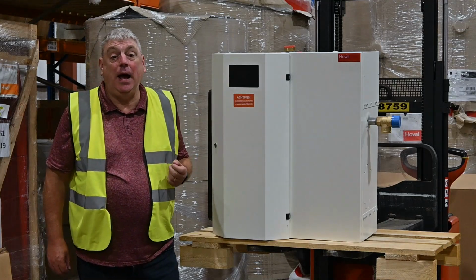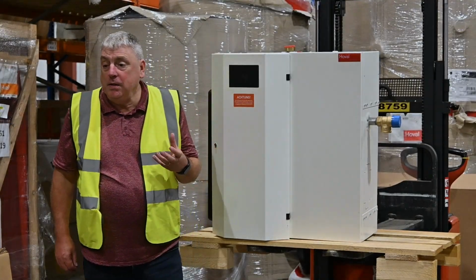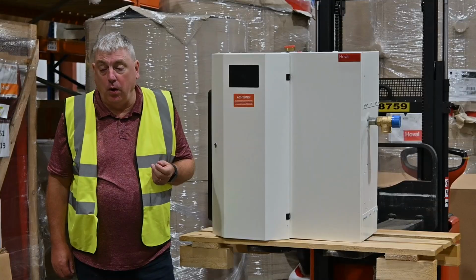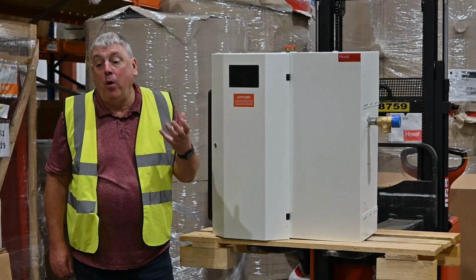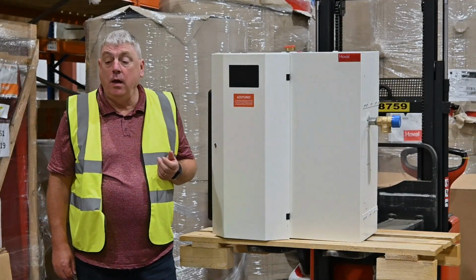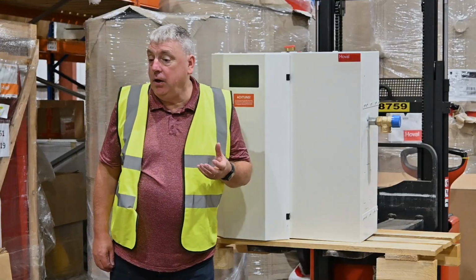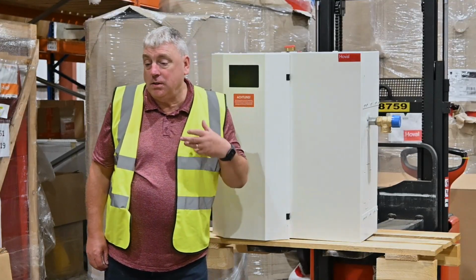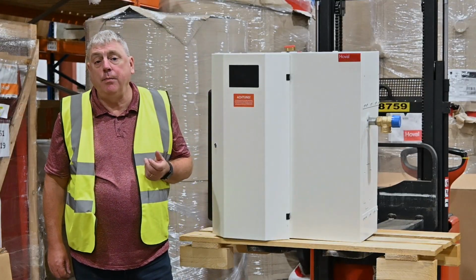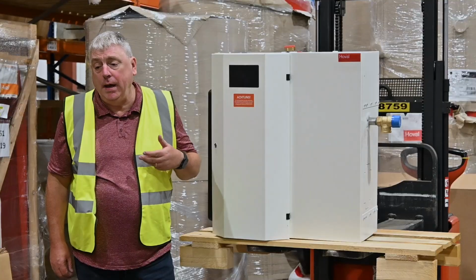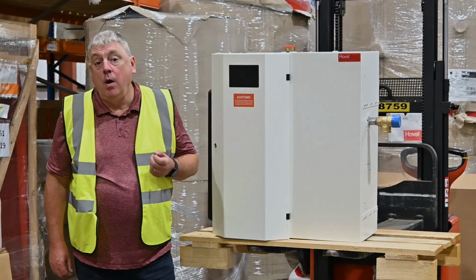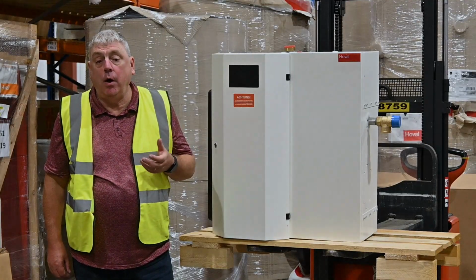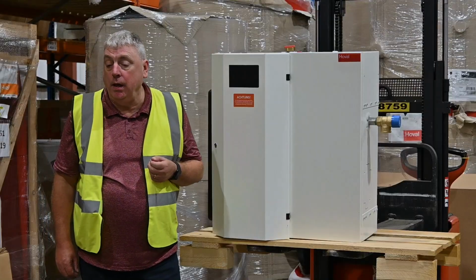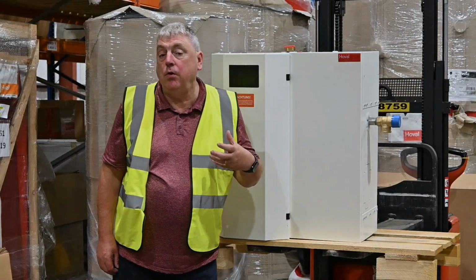This isn't particularly helpful if you're hoping to get the most from a condensing gas boiler, or certainly even more importantly where you're trying to run it in a system that includes a heat pump. Because operating at those sort of water temperatures, the heat pump may not even work, but it'll certainly work at a much lower efficiency, a lower COP, than might otherwise be the case if the water was a lot cooler.